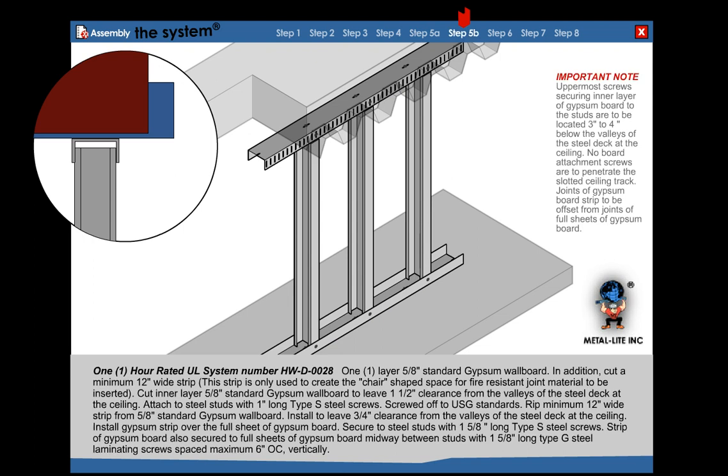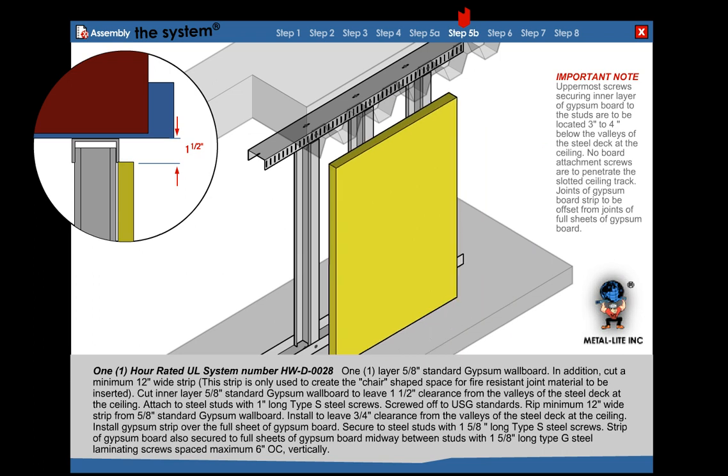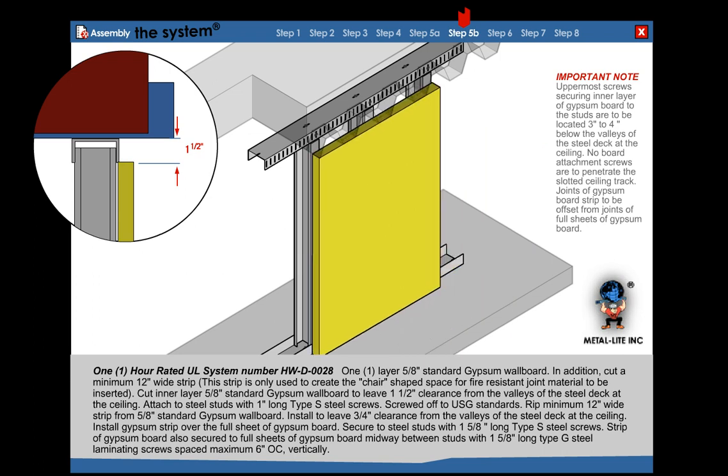Step 5b: For a 1-hour rated assembly, cut inner layer of 5/8 inch standard gypsum wallboard to leave 1-1/2 inch clearance from the valley of the fluted deck. Attach to steel stud with 1 inch Type S screws, screwed off to USG standards.